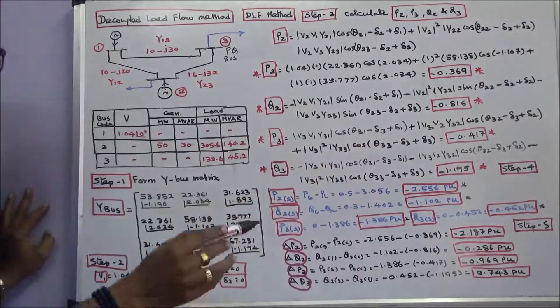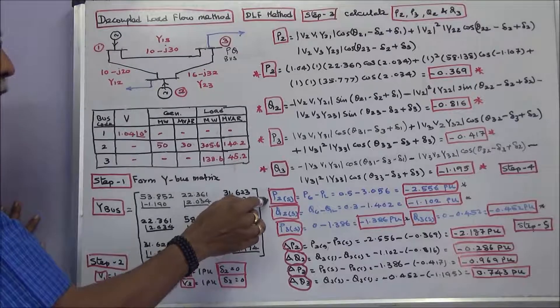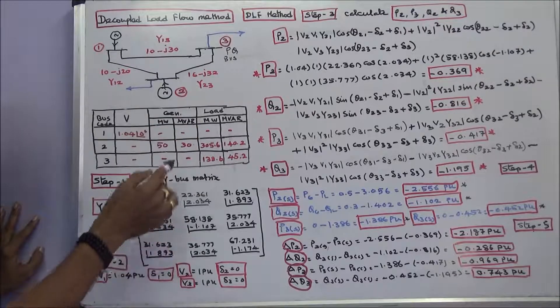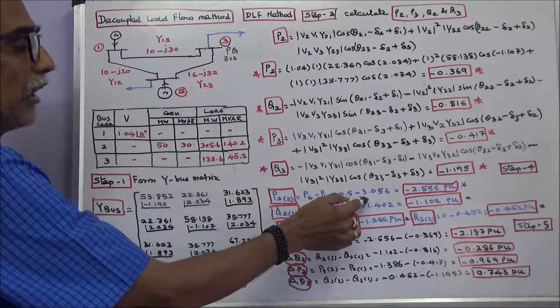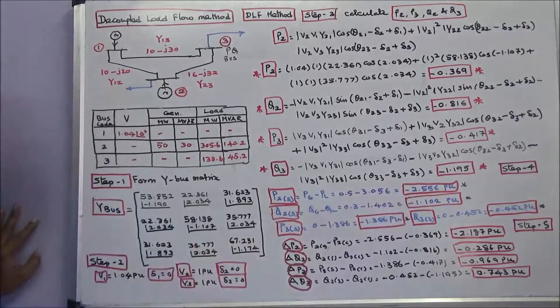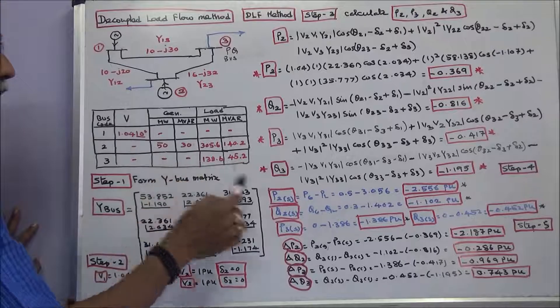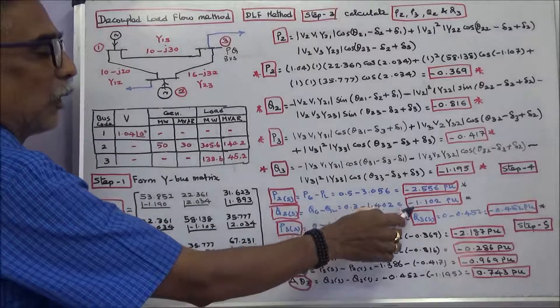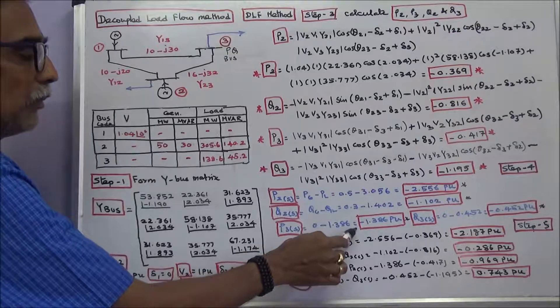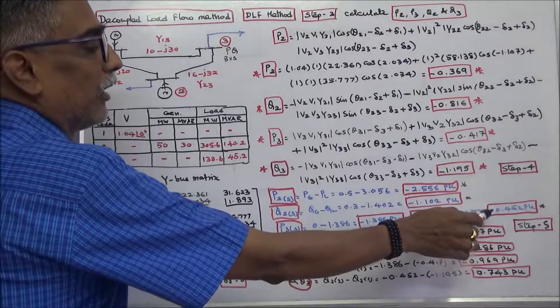Step 4: Calculate the specified real and reactive power. P2 specified equals P2 generation minus load. Generation is 50 MW, MVA base is 100, so 50/100 = 0.5 minus 3.056, giving P2 specified = -2.556 per unit. Q2 specified equals 30/100 minus 1.402 = -1.102 per unit. P3 specified equals 0 minus 1.386 = -1.386 per unit. Q3 specified equals 0 minus 0.452 = -0.452 per unit.